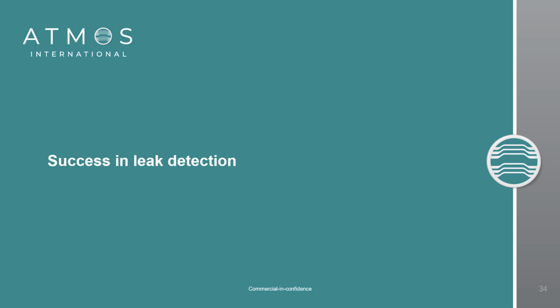So before I move on to this next slide, what I've demonstrated to you is that Atmos has looked at weaknesses in the leak detection technology available and tried to make dramatic improvements to it. So firstly, it's made improvements to a flow balance system by combining it with high acquisition rate hardware. We provided hardware solutions so that we can now install instrumentation where previously it wasn't possible, and to provide leak detection to pipelines where it might not have been previously possible through the use of JSPs and Eclipse units.